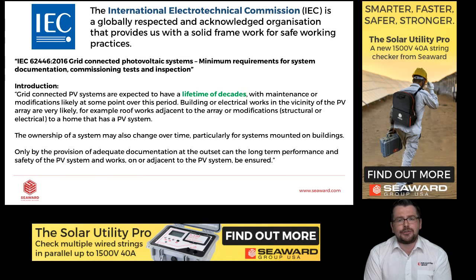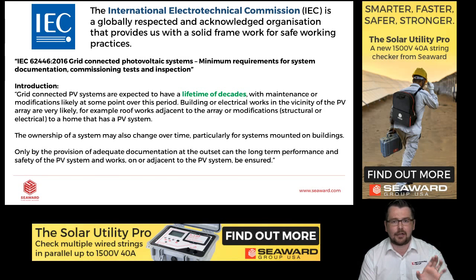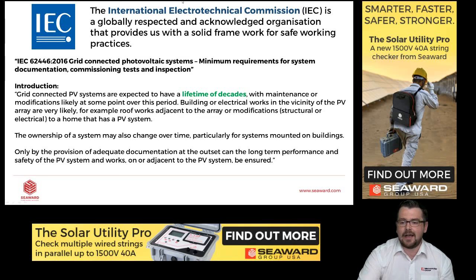And a very good one to look at, and I'm not going to labor too hard on this, I would advise making a note of this standard and going out and taking a look for it, is the IEC 62446-1 2016. So they give us an outline of how we should test and commission PV arrays of all sizes. So please do take a look at this standard, and this will give you an outline of what we should be looking for and testing too.